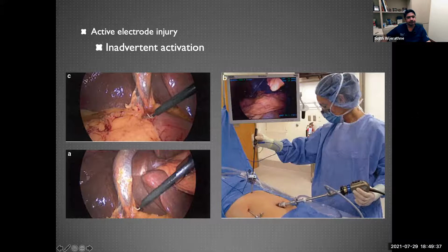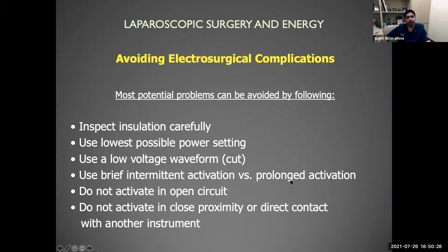So how do we avoid these undesirable effects or injury during electrosurgery? Most of these potential problems can be avoided by following some guidelines: always inspect the insulation carefully, and if equipment is available to test for insulation, please use it. Use the lowest possible power setting, a low voltage waveform such as cut mode, and use less energy. Use brief intermittent activation rather than prolonged activation, do not activate in open circuit, and do not activate in close proximity or direct contact with another instrument.